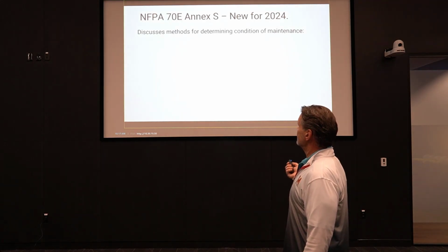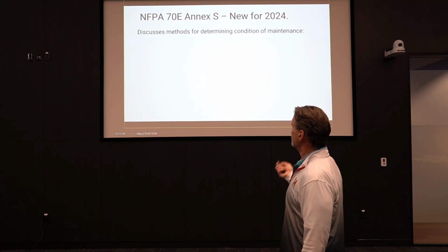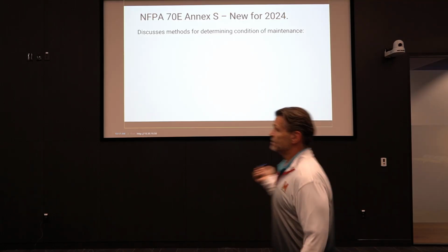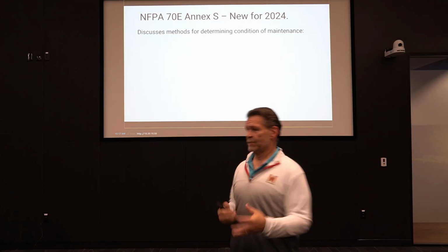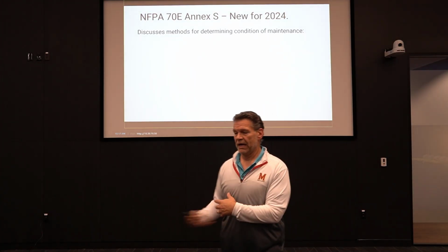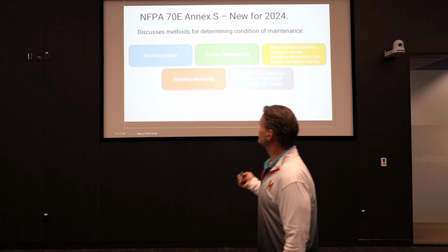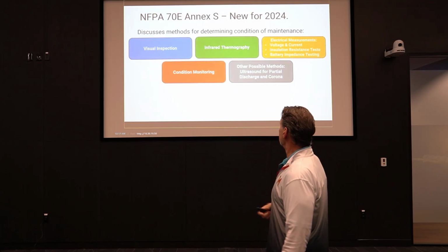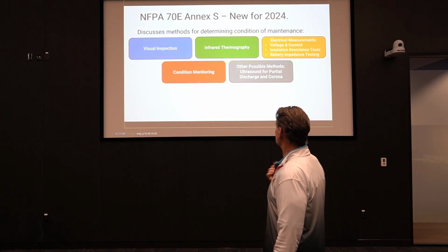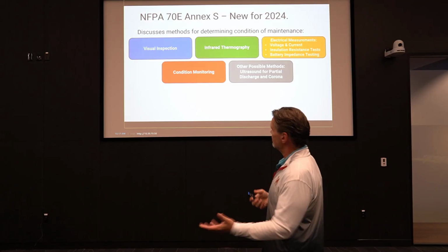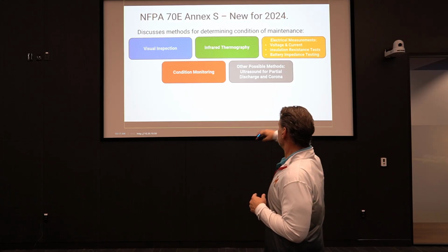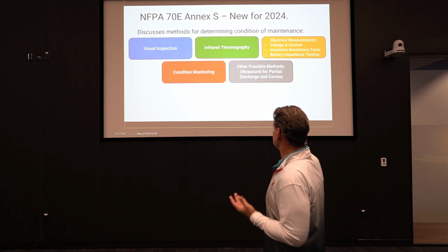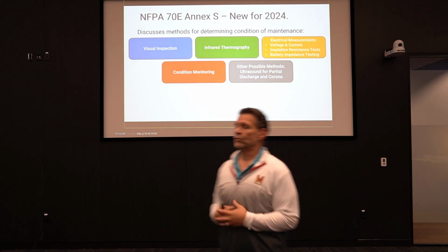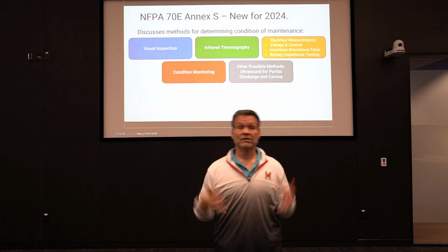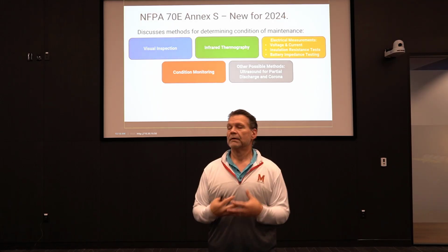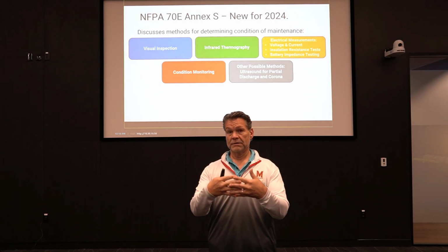So Annex S, NFPA 70E, new for 2024, discusses how we determine the condition of maintenance. This is something that goes hand in hand with NFPA 70B. Methods include visual inspections, infrared thermography, electrical measurements, voltage and current, insulation resistance, battery impedance testing, condition monitoring, and ultrasound for partial discharge and corona. So a lot of things that we can do. NFPA 70E is now incorporating that because they know that the two are going to be working directly together to keep things safe.